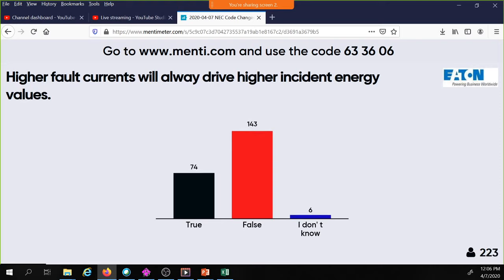Now, if you are in, say, the instantaneous region of a circuit breaker and your clearing time is constant, yes, a higher fault current will give you a slightly higher arcing current, which at the same clearing time will get you a higher incident energy. But the change is only in regard to the amount of current because your time is constant. In some cases, which we'll show you, when you lower your fault currents, you can be in much longer clearing times on the overcurrent device, and that will generate a lot of incident energy.